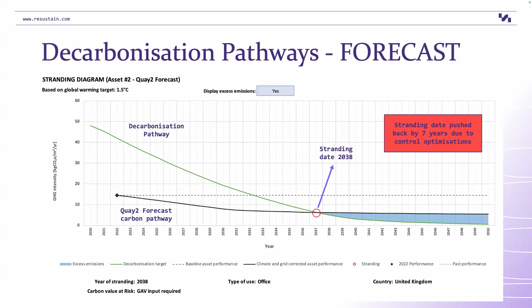So this is what happened. We started our control optimizations, produced the savings report for it, and went to Edinburgh to physically work on the BMS. What we found was that the heat exchanger logic wasn't programmed correctly. We hadn't looked into that in enough detail; we just made our change, and found out it wasn't programmed correctly.